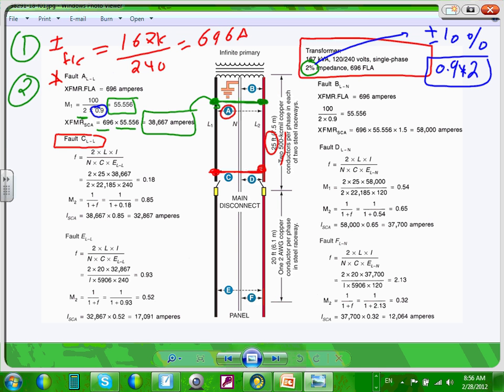Now I move 25 feet, and I need to find the short circuit because there's another panel. Why do I want to do it 25 feet? Because I put another panel there. This is at the main panel. It's 38,000. Sub panel downstream, I need to find it. When you go downstream, guys, the conductors act as an impedance to choke the current.